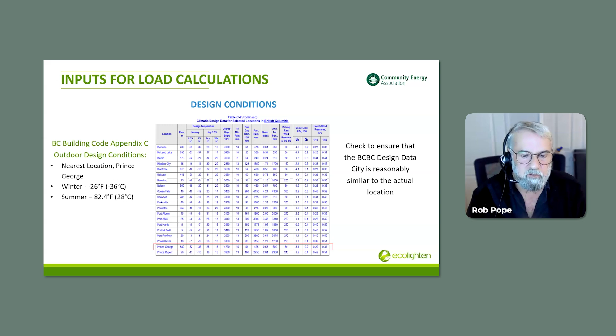So what you have to do is go to the nearest one. In this case, for this town, there's no entry in this table in the code, so it's the nearest larger city. The outdoor design conditions: winter is minus 26 Fahrenheit, minus 36 Celsius - pretty cold, it's really cold, I've been there in those conditions. In the summer, it's 82.4 Fahrenheit or 28 Celsius.